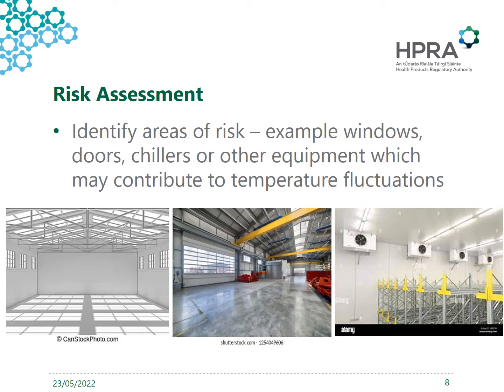After this, the company should look at the risk assessment to identify the probe placement for the duration of the study. So it's expected that they identify areas of risk. For example, the proximity of a storage area to things like a window, internal or external doors, or equipment such as aircon, chillers, etc., which may contribute to temperature fluctuation.